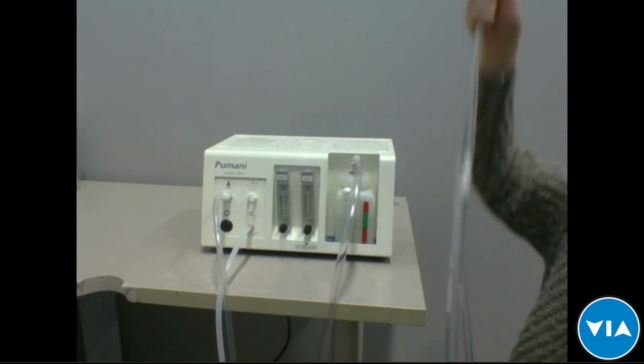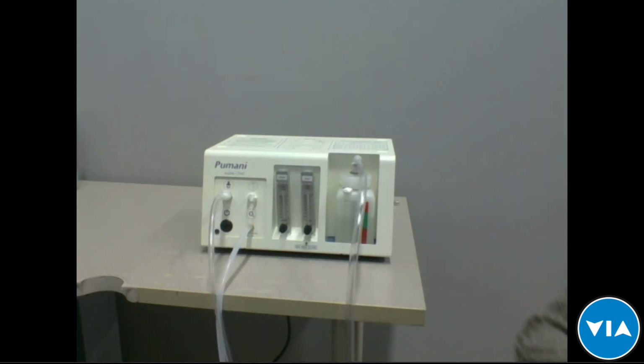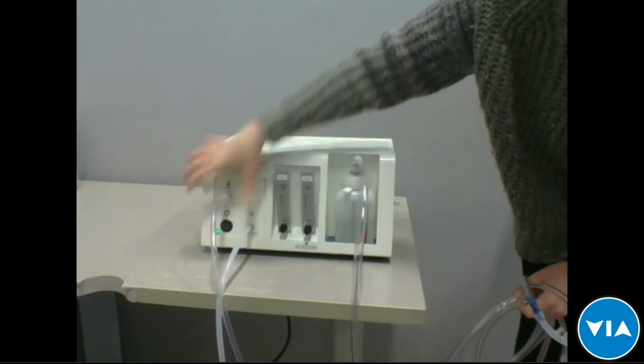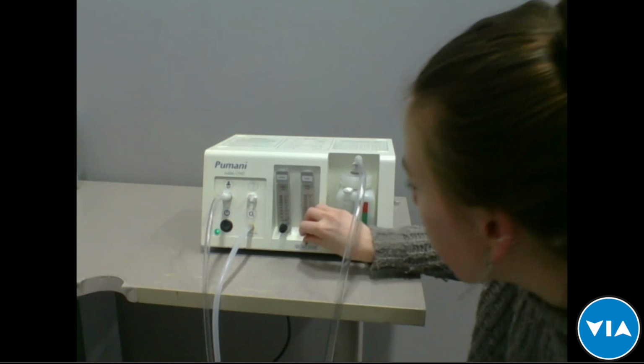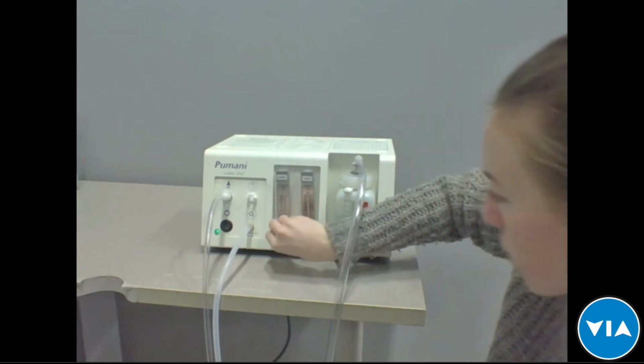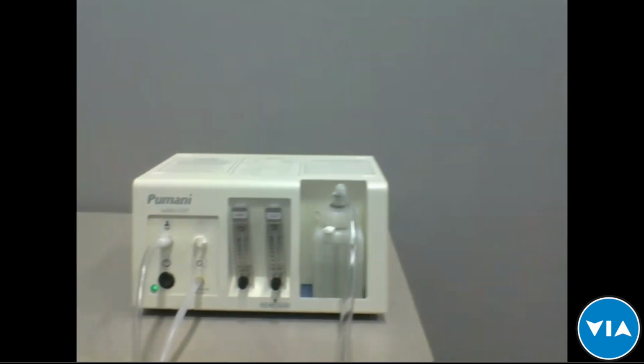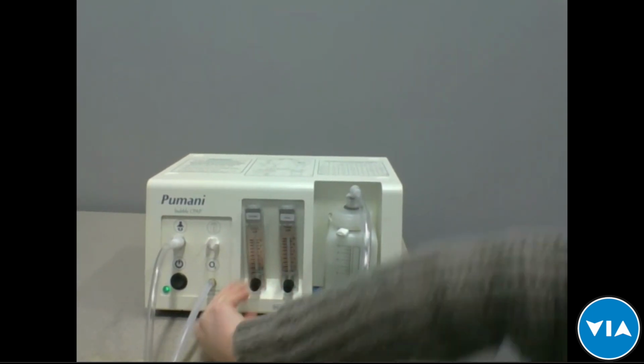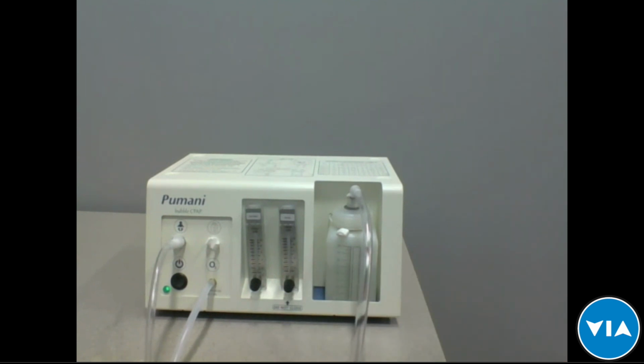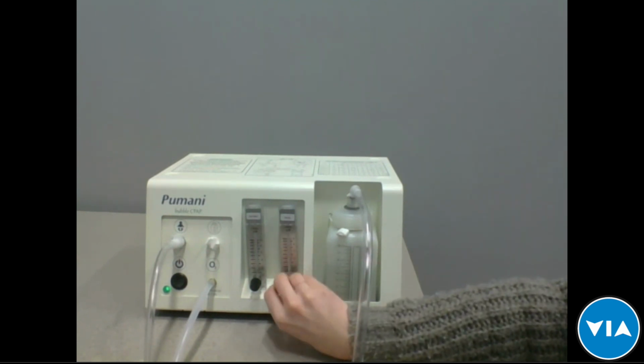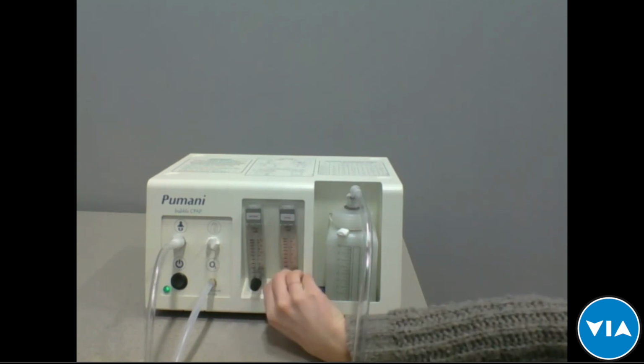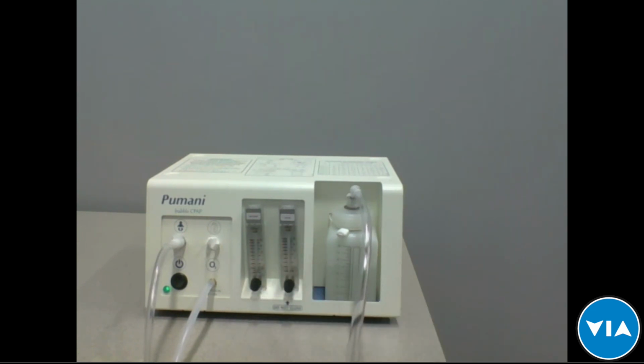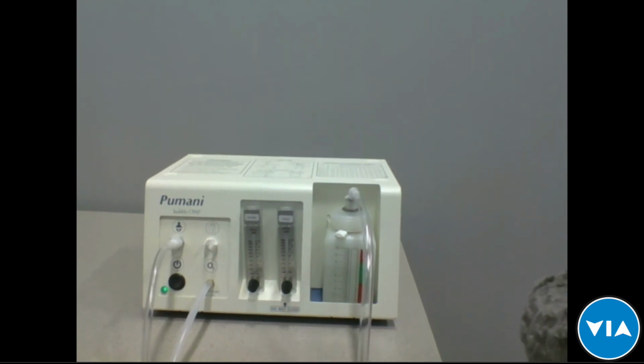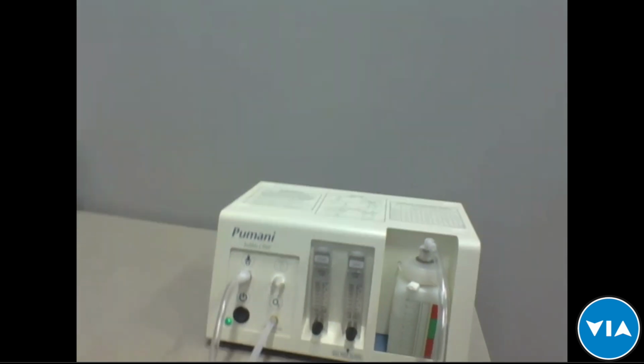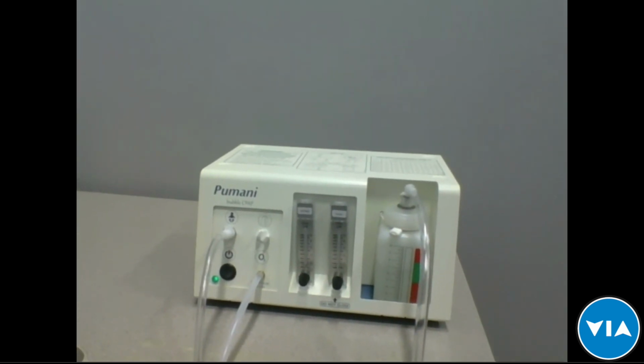Once that's there, before putting on the baby, you turn on the Pumani device. And you open both of the flow meters. By opening, it's basically turning it all the way to the left, as you see Alexandra doing. And that's important to do before you connect the oxygen or turn on the oxygen, to make sure that entire pathway is open so the balls will move. And at this point, you likely see that the ball in the total flow meter is moving, but not the one in the oxygen. It's okay if we can't see now, but that's what you should be seeing.